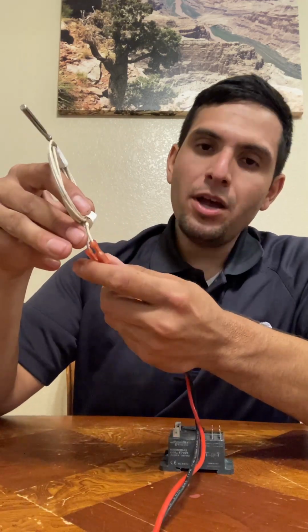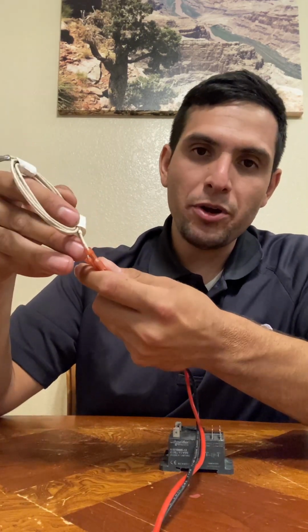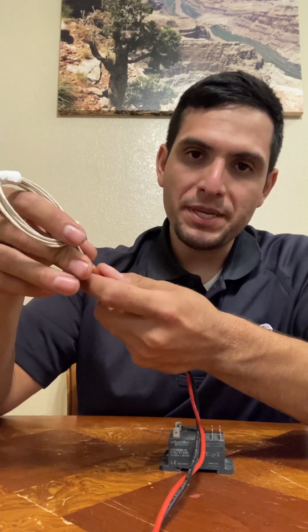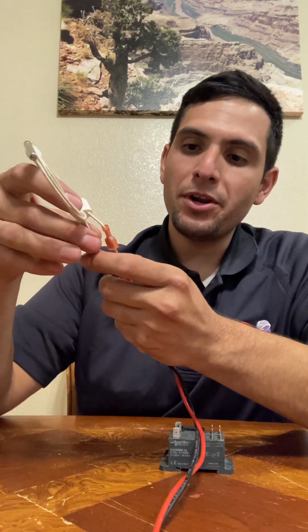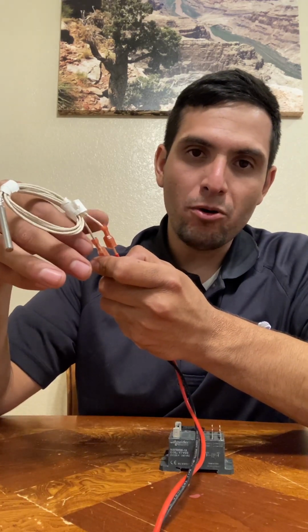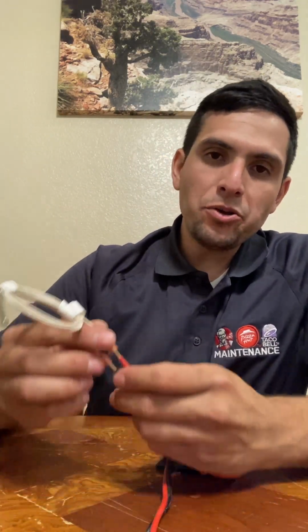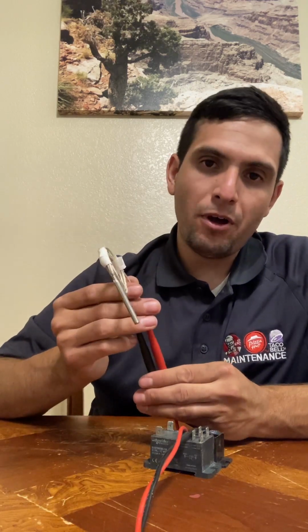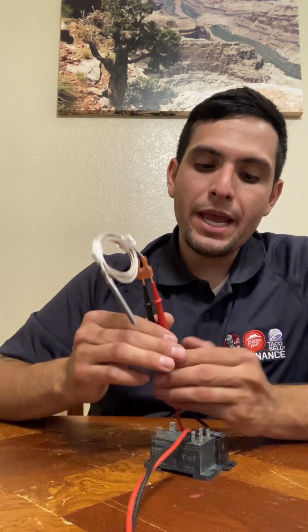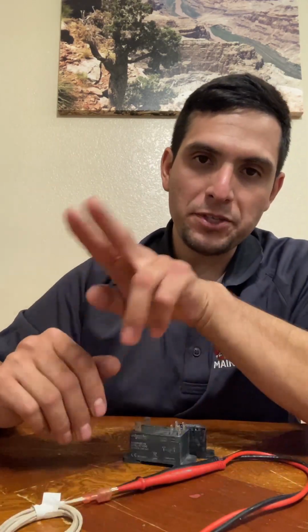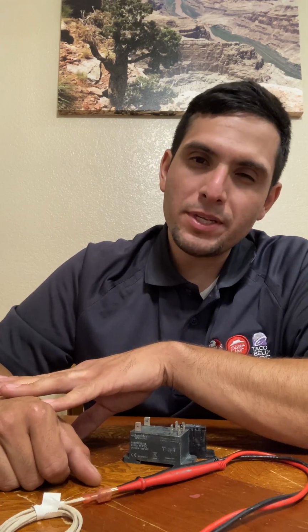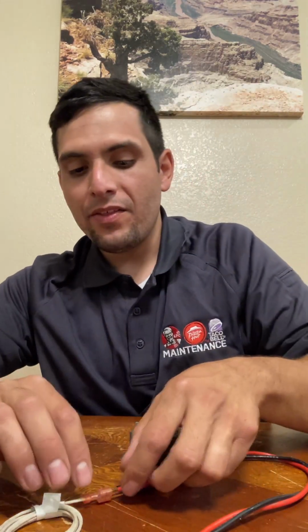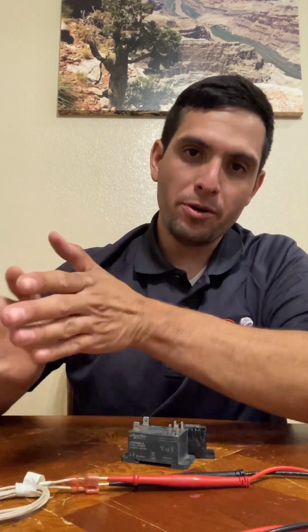So you'll take your ohm reading, and like I said, we don't know the exact resistance we should have unless we're at room temperature. At room temperature, we should have 2,100 ohms. But if it's hotter than that, if it's already started heating, or it's close to temp, you're going to have different readings. So what I do is I just check all of them. Check all 3 of your probes, and whichever one is different than the other. If you have 2 that are the same and 1 that's off, that one's where to start investigating more. And that doesn't necessarily mean that your probe is bad, because it could just be that the heating element's not engaging, or that relay is not engaging and heating up. So of course it's going to read differently, but that's where your problem is at least.